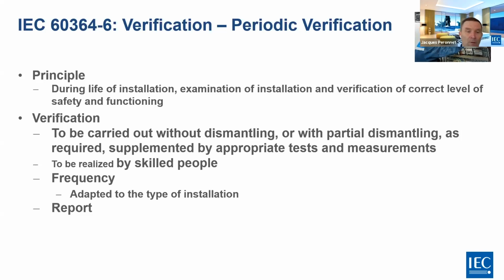of installation. Once again, in 60364, this periodic verification is not mandatory, not like initial verification, but we advise national committees to push for some periodic verification, depending, of course, on the type of the building. In a dwelling, this frequency will be much longer than for a commercial building or a public building. And then also we describe in this standard how to make a report, what you have to include in the report, and how to fulfill this report.